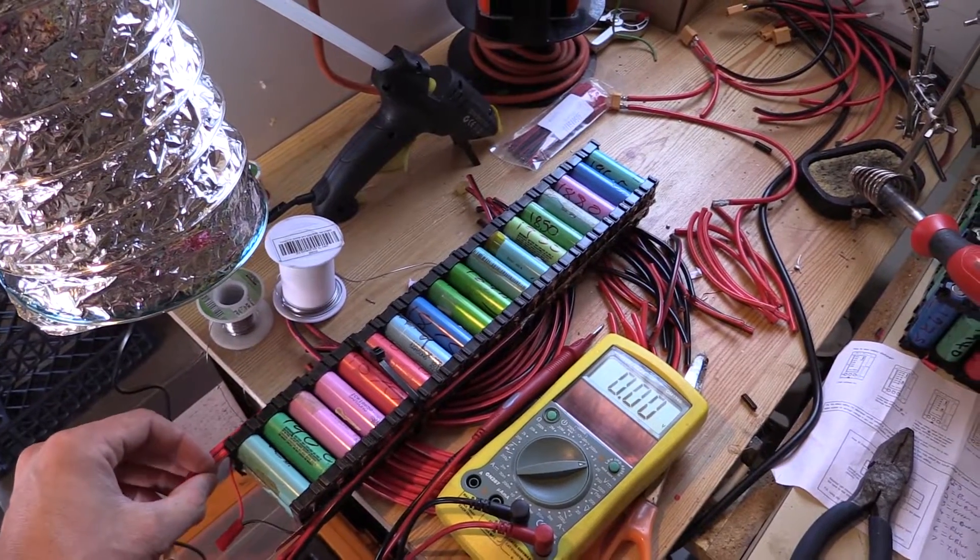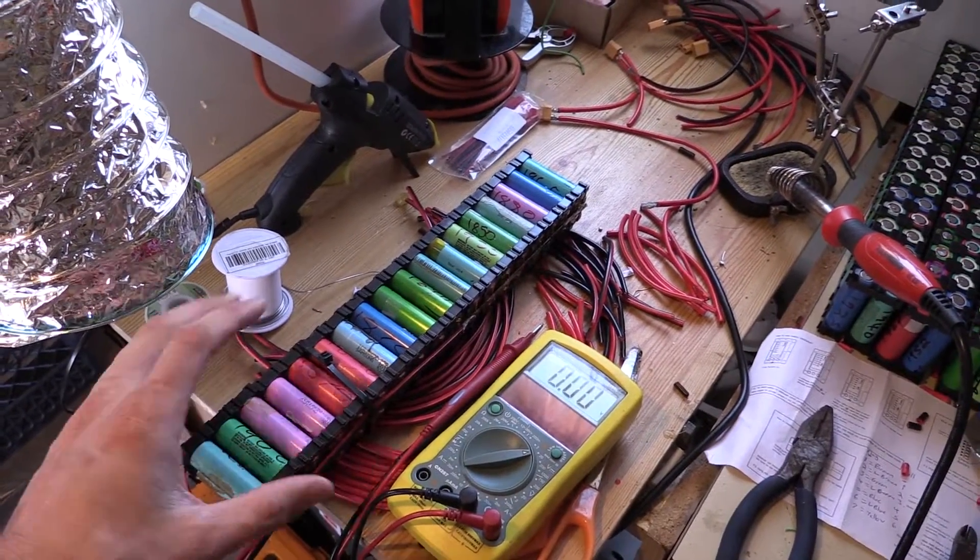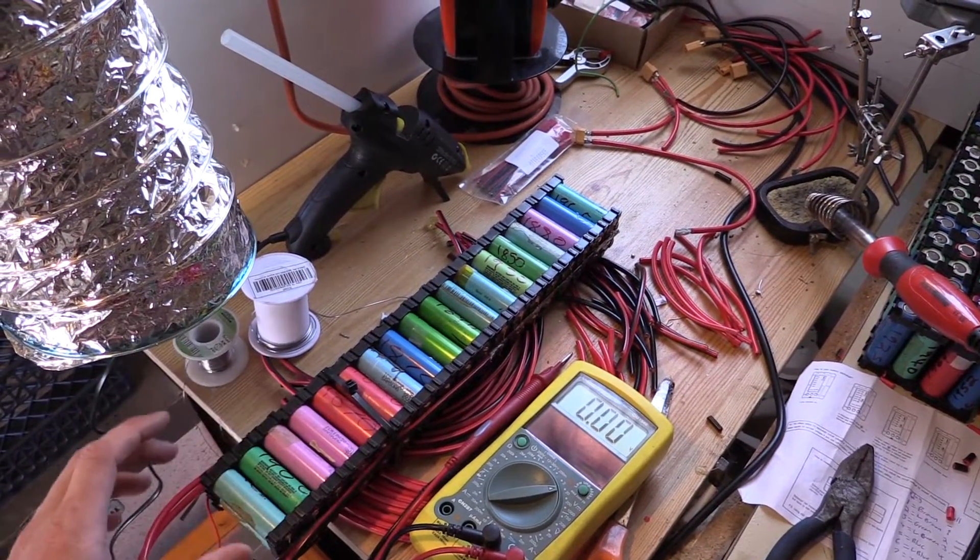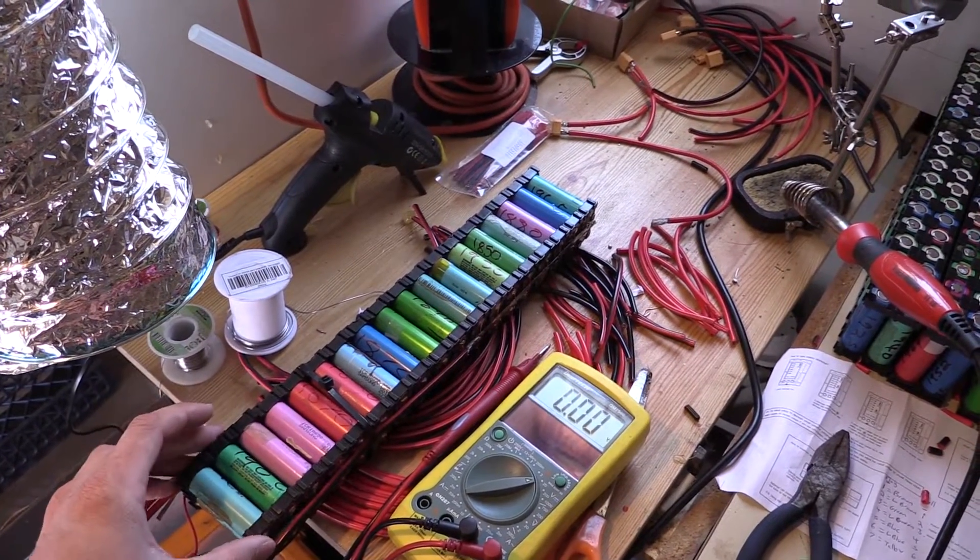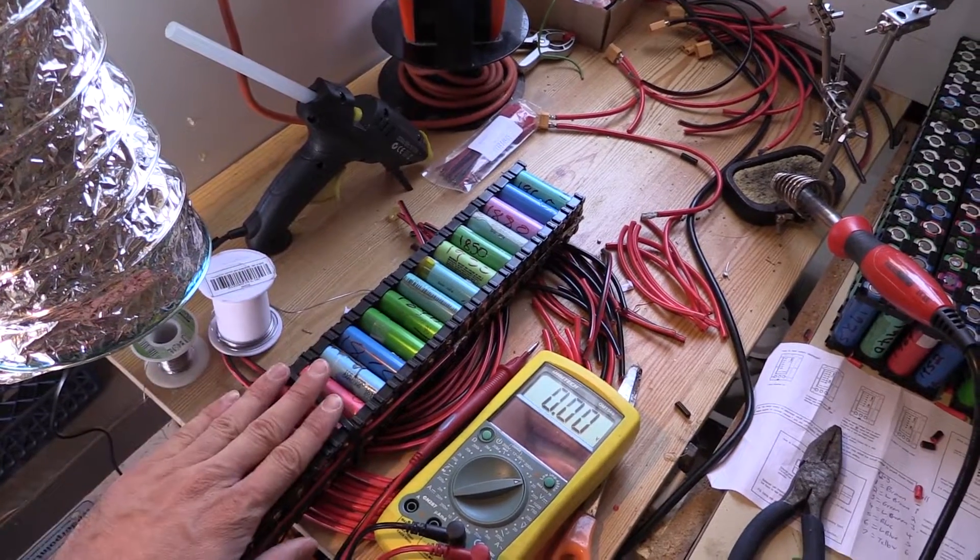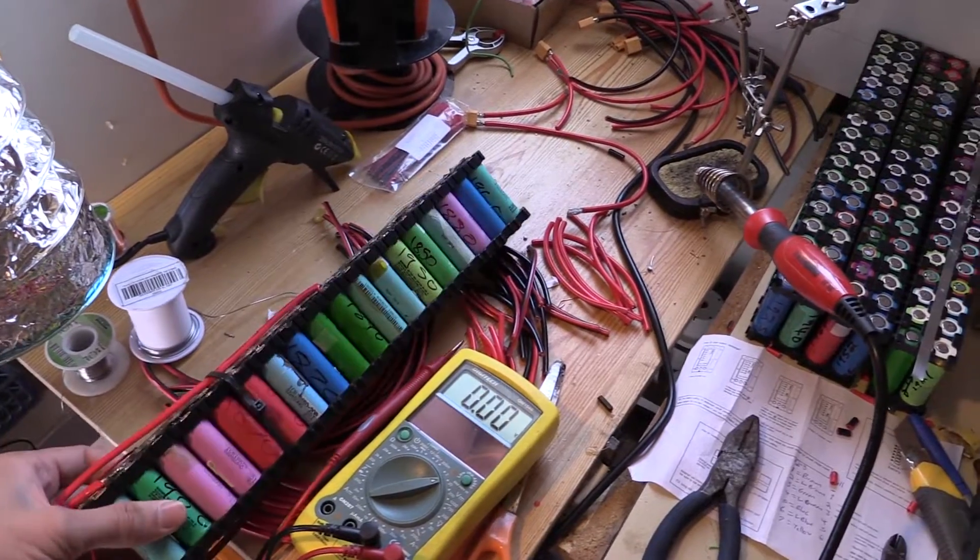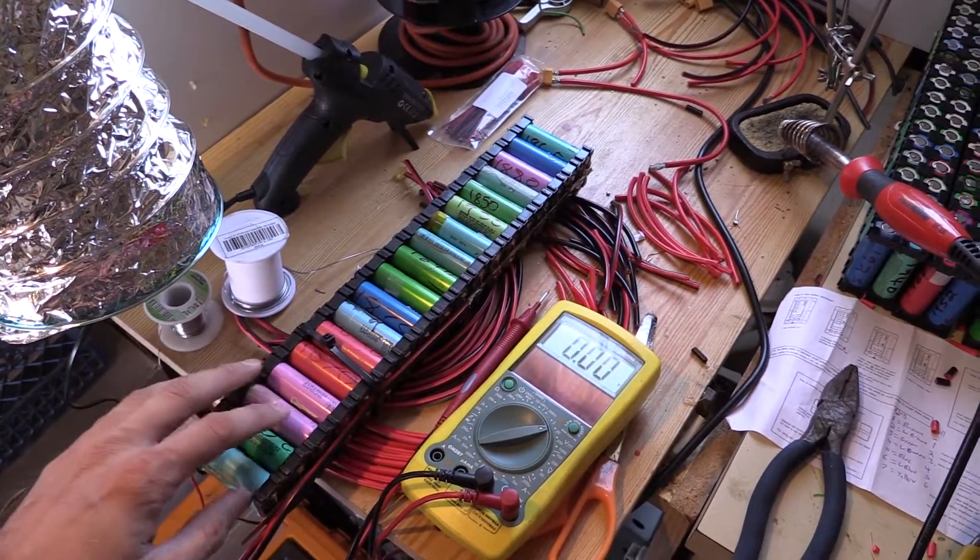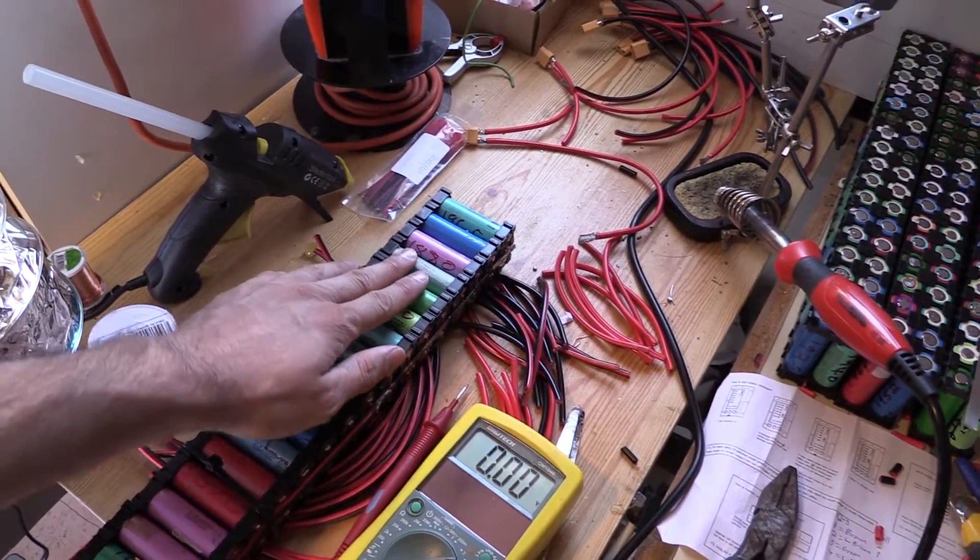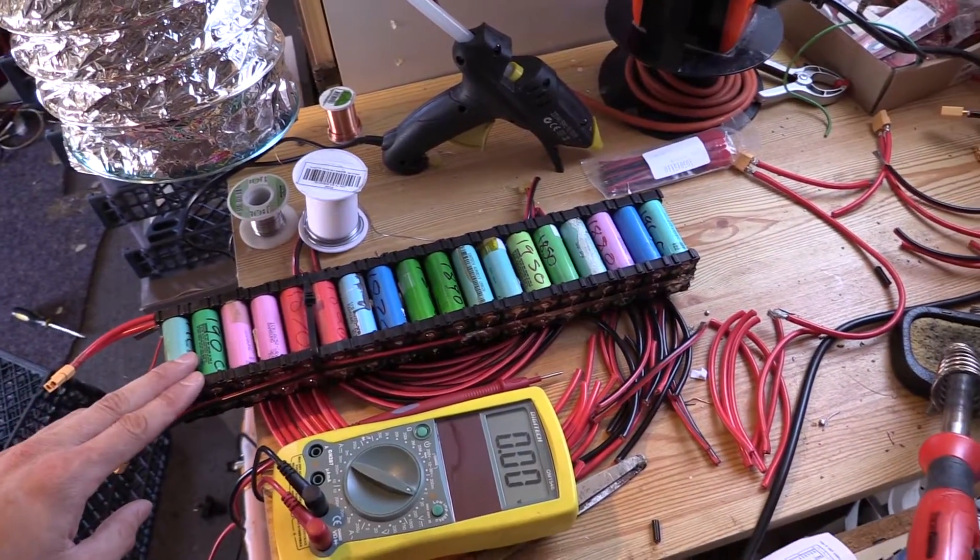This is a really big problem that you can't prevent apart from setting up monitoring so you're constantly watching each pack. As soon as something goes out of balance too much, you can turn the system off and isolate the pack. I'm lucky because I've got small pack sizes—most are around 32 cells, the lower capacity ones have about 34.